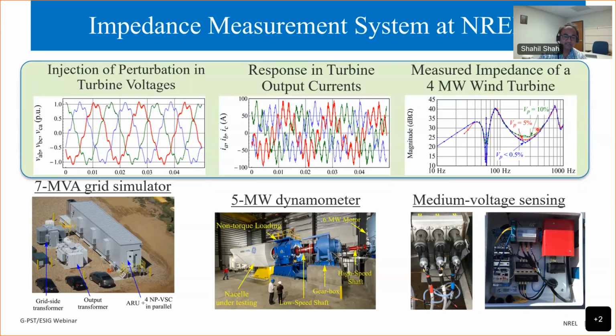As I said earlier, we are trying to get this test into the IEC standard for wind turbine testing, so that whenever we are doing tests like low voltage ride through or how a wind turbine behaves during a frequency event, we should also be performing impedance scans, because that is very critical to understand how that wind power plant will impact the stability of the grid, or the small signal stability of the grid.